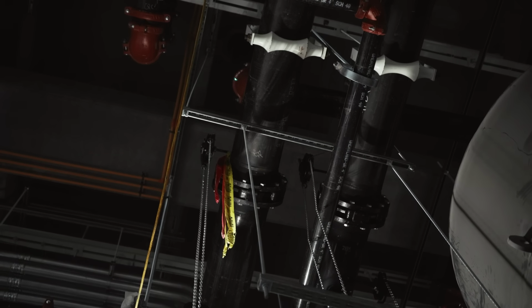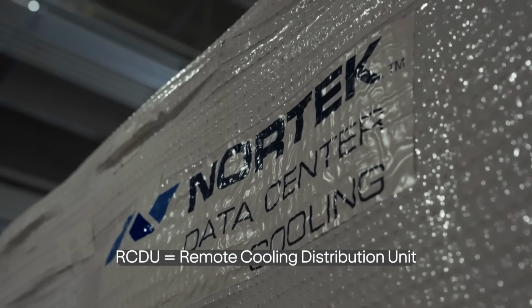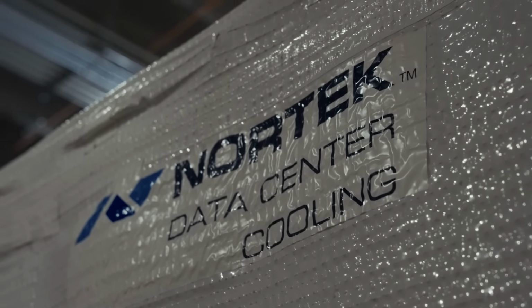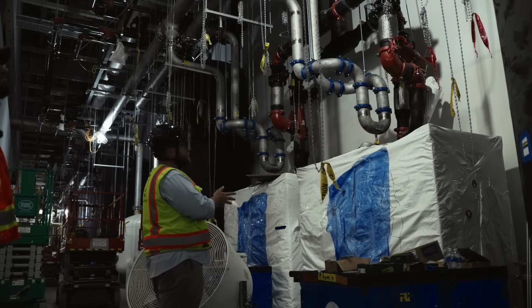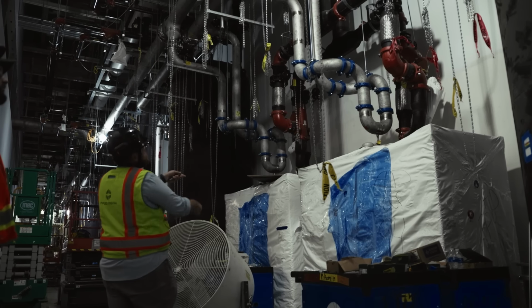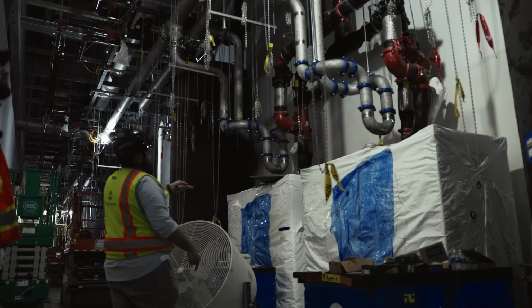From there, it's fed to an RCDU, which is a remote cooling distribution unit, where there's a heat exchanger inside that transfers the heat away from the tech loop, which is in the stainless, and then puts it into the return that goes back up to the roof.